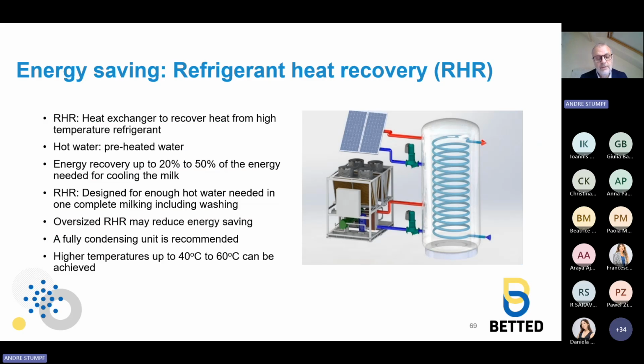So a refrigeration heat recovery unit can be used as a heat exchanger to transfer the waste heat from the hot refrigerant line between the compressor and the condenser to the hot water storage tank. So yes, we have a lot of hot water demand in the farm. And this water can be used as a preheated water source feeding into the water heater. A refrigerant heat recovery unit can cover from 20 to 50% of the energy that would be needed to cool the milk for storage.